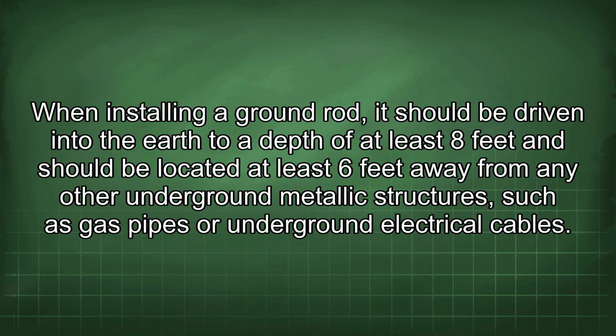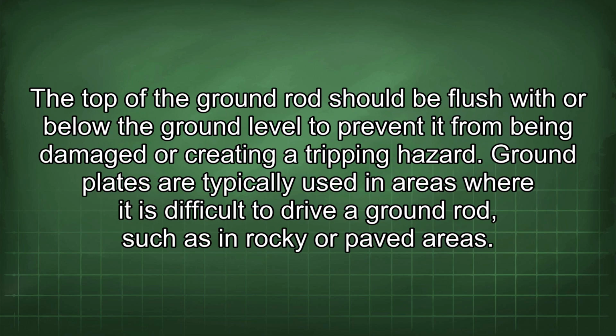When installing a ground rod, it should be driven into the earth to a depth of at least 8 feet and should be located at least 6 feet away from any other underground metallic structures such as gas pipes or underground electrical cables. The top of the ground rod should be flush with or below the ground level to prevent it from being damaged or creating a tripping hazard.